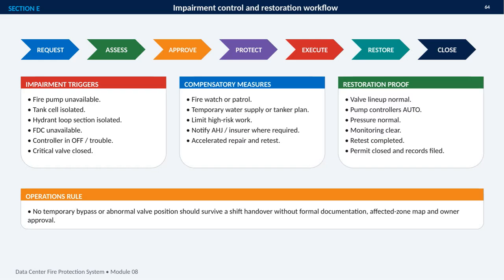This slide defines the impairment control and restoration workflow for the fire protection system. The process moves through 7 controlled steps: request, assess, approve, protect, execute, restore, and close. That sequence ensures an impairment is not treated as an informal maintenance task, but as a managed operational risk. Typical triggers include an unavailable fire pump, an isolated tank cell or hydrant loop, an unavailable fire department connection, a controller in OFF or trouble, or a critical valve that has been closed.